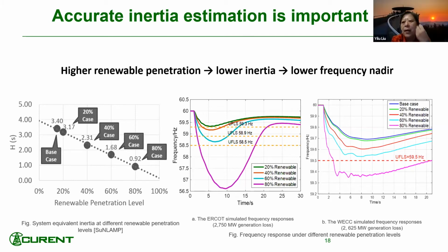Yes, that's the key. GPS synchronization makes it possible to observe the grid in one snapshot at a time, because once you collect the data and send it to the server, you're probably delayed by a few hundred milliseconds. Some are less, some are longer, but it's mostly within 1 second—you do have quite a delay. Because GPS timestamps are already put in the data on every data point sent out, you can piece them together automatically to get each frame from a geographic area as well.